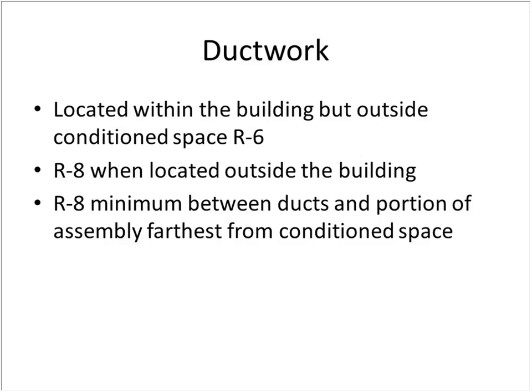And you have to have a minimum R8 between ducts and the portion of the assembly farthest from the conditioned space. So if you have ductwork that's in a wall cavity, exterior wall cavity or floor cavity, the minimum insulation between that duct and the ambient air, if you will, would be an R8. So if you're running a second floor duct up through a garage connected wall, and you've got a 2x4 wall assembly, and you're putting in a 2.5 inch thick duct in there, you'd have to have an R8 between that duct and the drywall to the garage section. And that also would be considered duct outside of the building then.